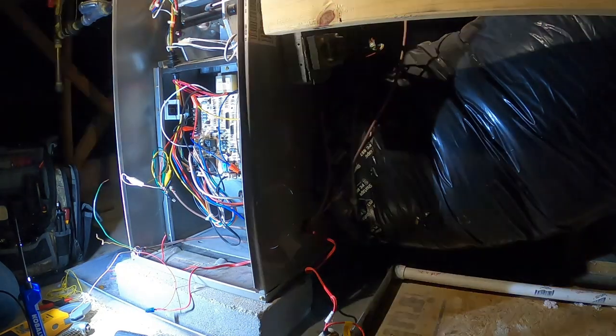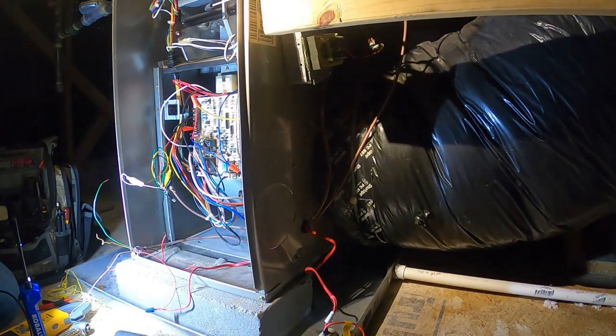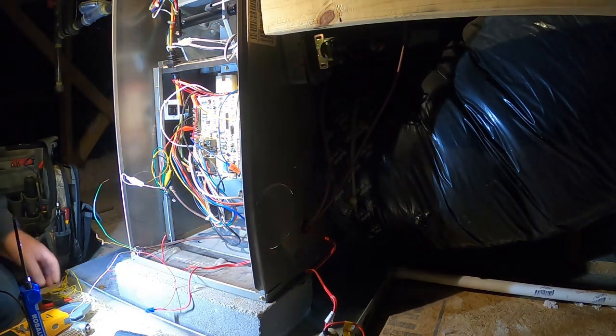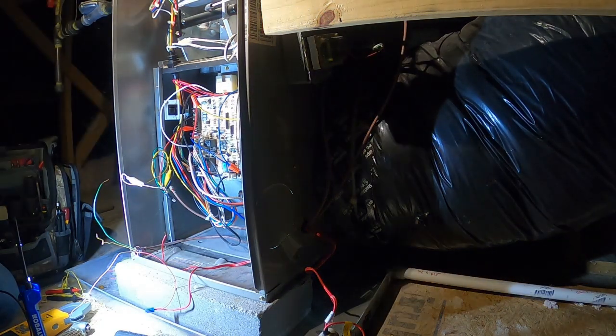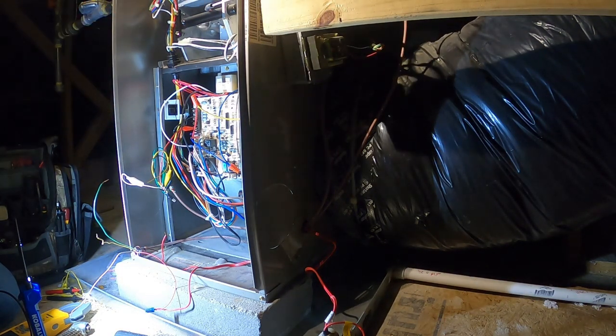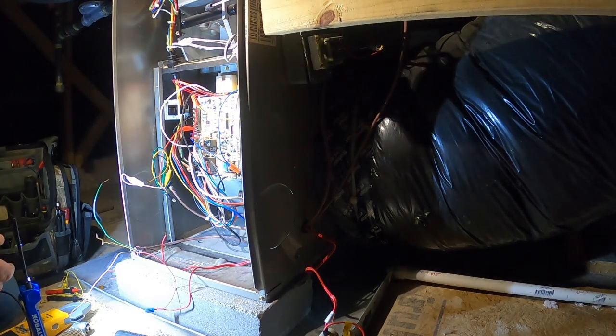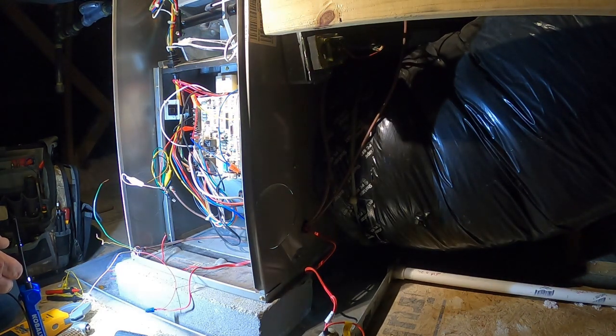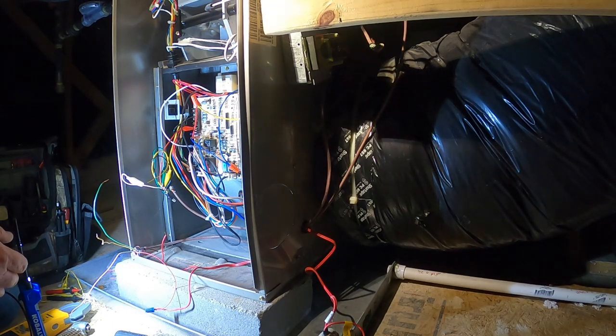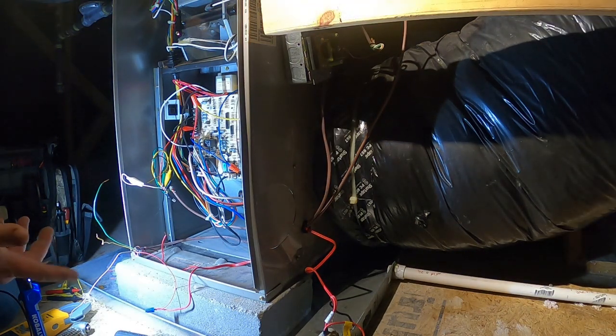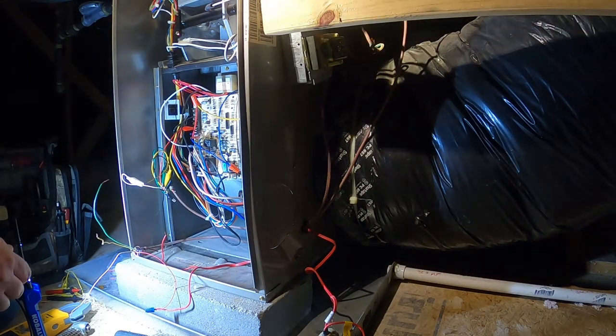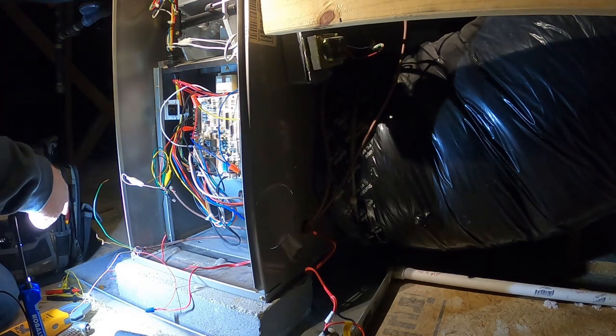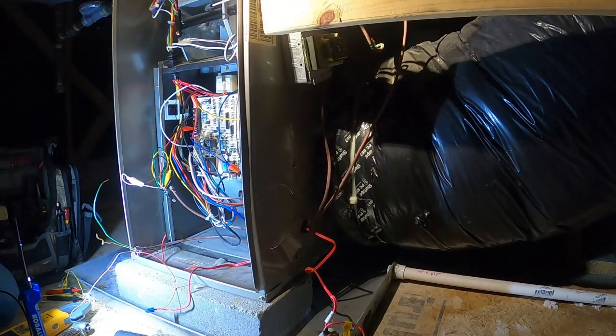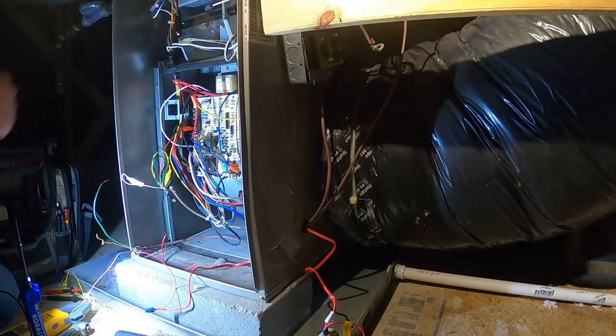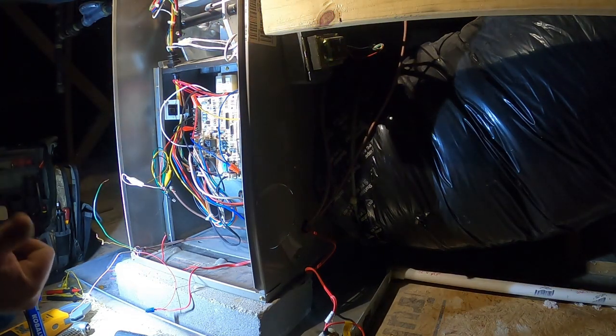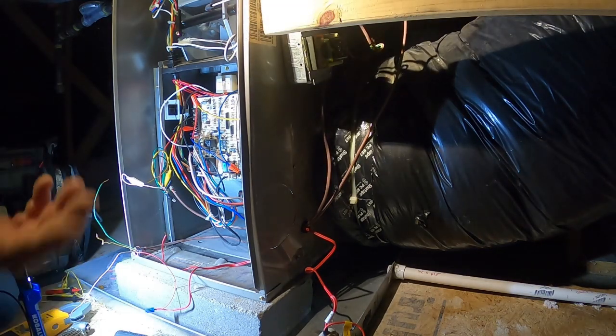So we'll wire all this up, and then we're going to run it through the thermostats. Hopefully whatever they did up here, shorting whatever they were shorting, didn't damage the zone system or the thermostats. But I mean, this is the problem. Somebody came out here, a jackleg Craigslist, I'm Super Tech, and you got a bad board and you need a new furnace, because he didn't know how to use a meter and go outside and check a contactor and determine what was causing the fuse to blow. It was a 3 amp fuse to begin with. He put a 5 amp in it. That wasn't enough protection. So when he put the power back to it, that fuse didn't blow before the transformer went, because the contactor was out there calling. He was trying to run the cooling, and the contactor caused the whole problem.